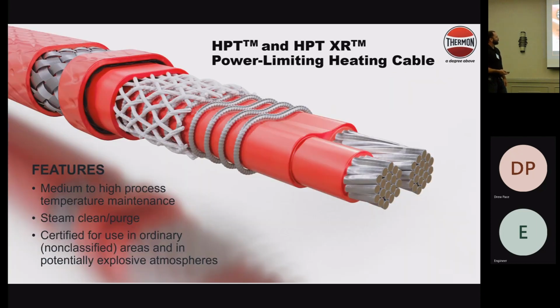To highlight the HPT a little bit more, just so you can see how it's built - what we do, and the component we've had issues with, is this element that's coiled around right here, like a spring-like coil. That's what's heating up. It touches the conductor on the nodes, like he spoke about yesterday. So we know how much coil is in between each node, we know the resistance and hence the power output.